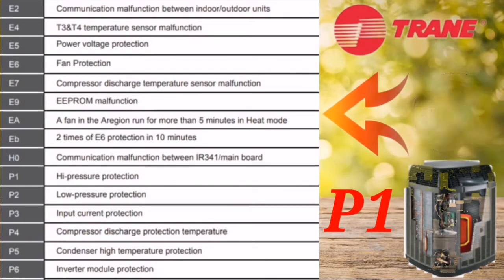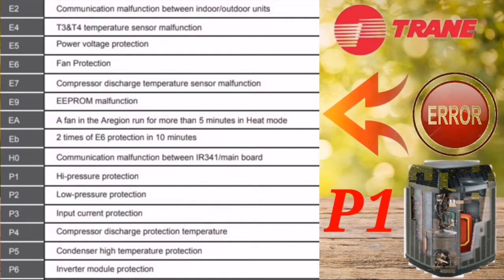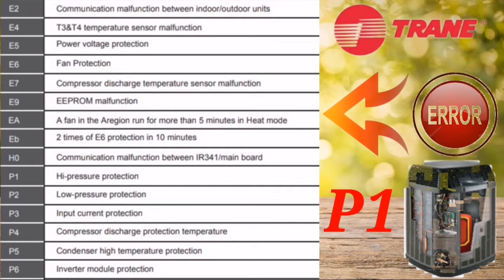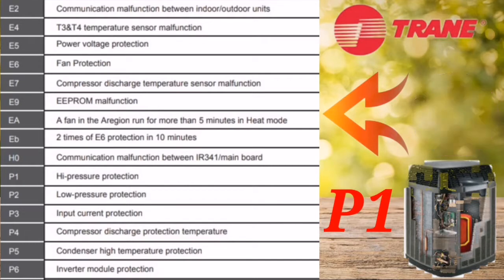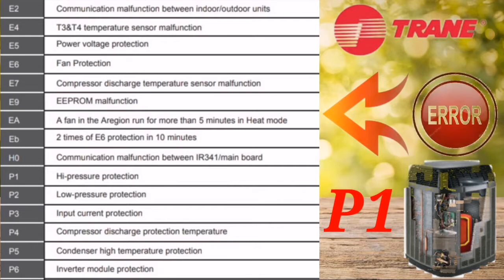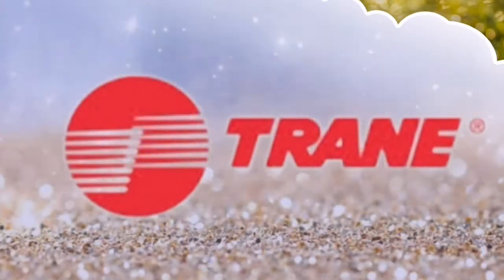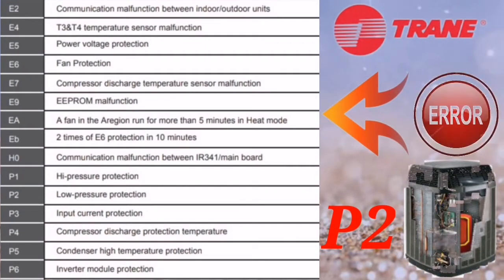The next error code is P1, which means high pressure protection. This can occur when the refrigerant quantity is too high, causing the system to protect the compressor. First, check the high pressure switch — verify it is connected properly and undamaged. Then check the resistance of the high pressure switch. Also verify the outdoor PCB is sensing the high pressure switch correctly. If the PCB is not sensing it properly, change the outdoor PCB.